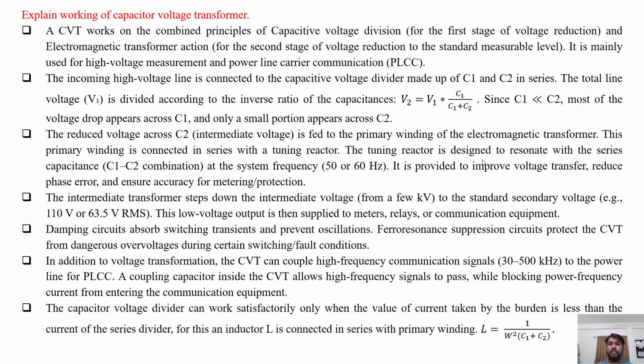The tuning reactor is designed to resonate with the series capacitance C1 and C2, the combination, at the system frequency 50 or 60 Hz. It is provided to improve the voltage transfer, reduce the phase error and ensure the accuracy and efficiency for metering and protection purposes. The intermediate transformer steps down the intermediate voltage from few kilovolt to the standard secondary voltage of 110 volt or 110 by root 3 volt RMS values. This low voltage output is then supplied to the meters, relays or communication equipments for the further actions.